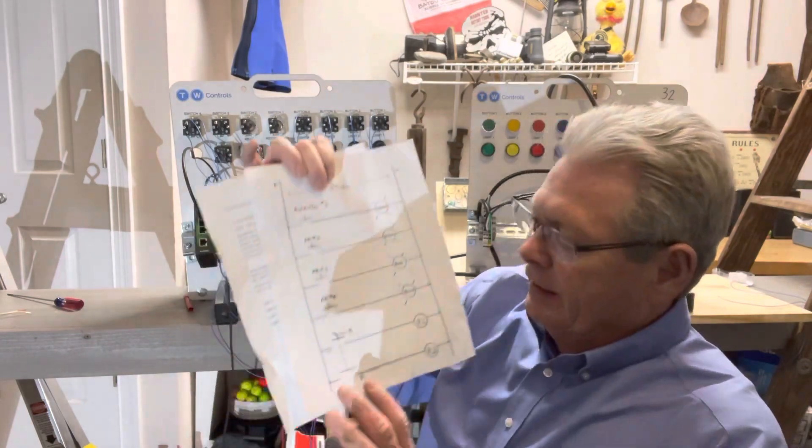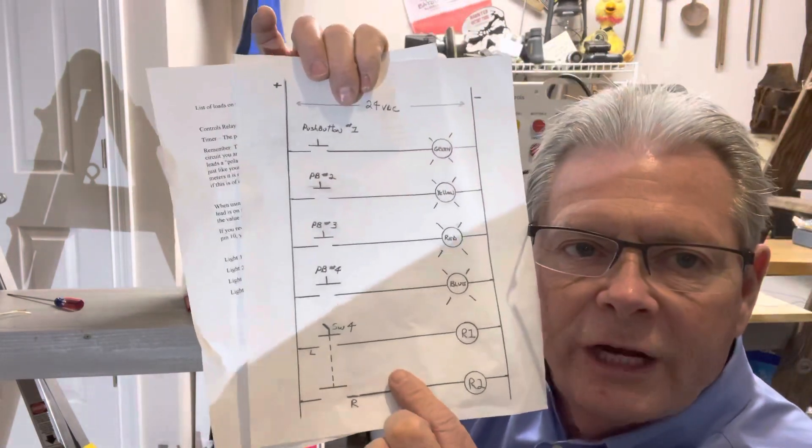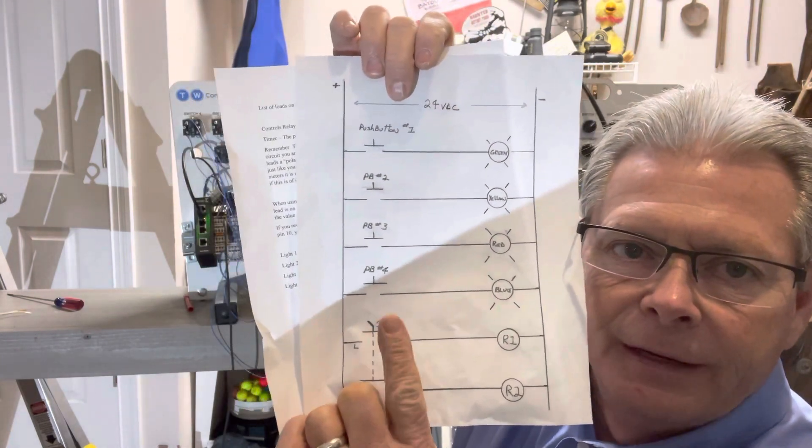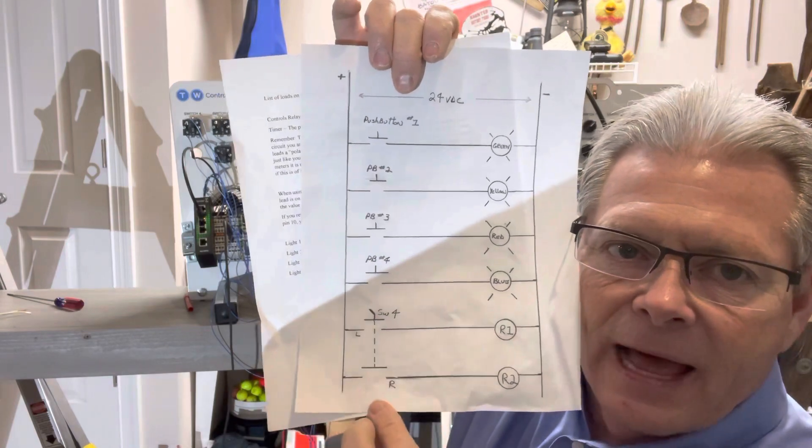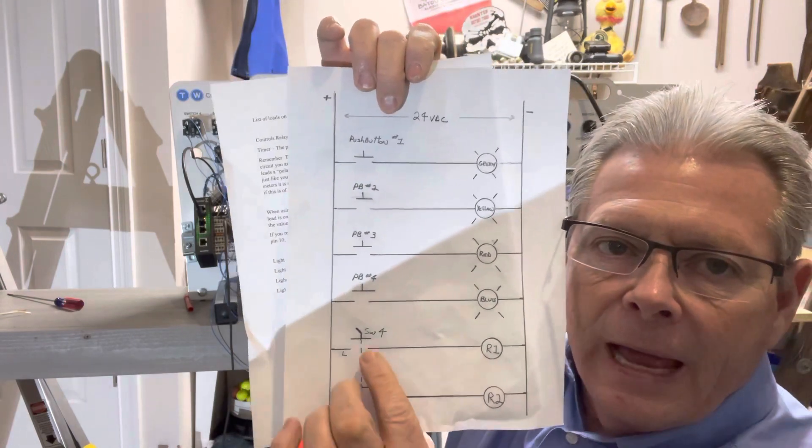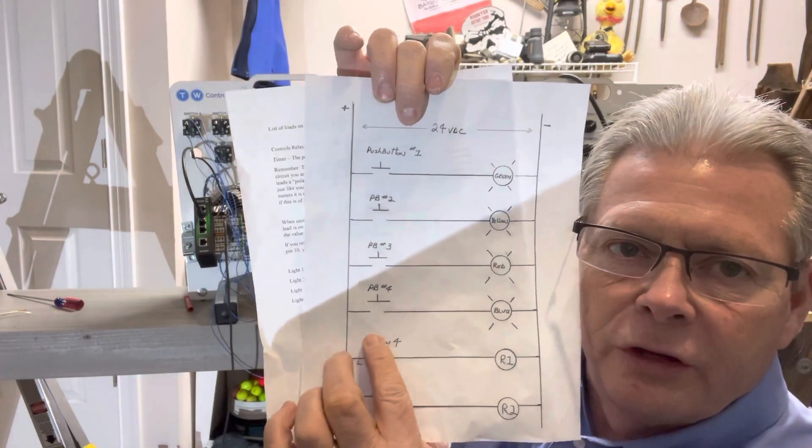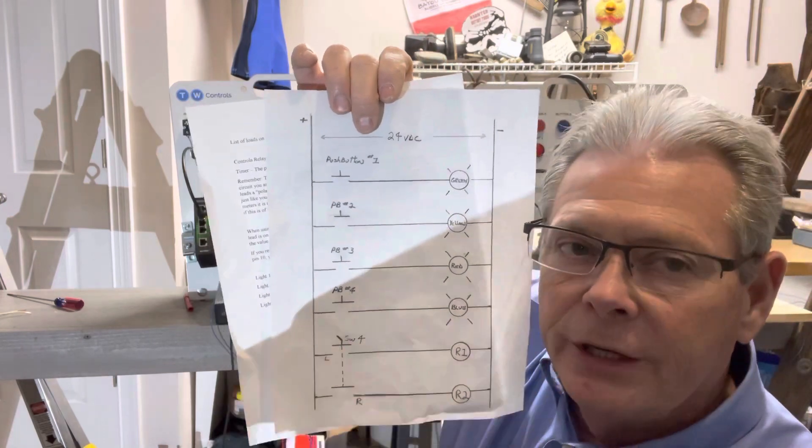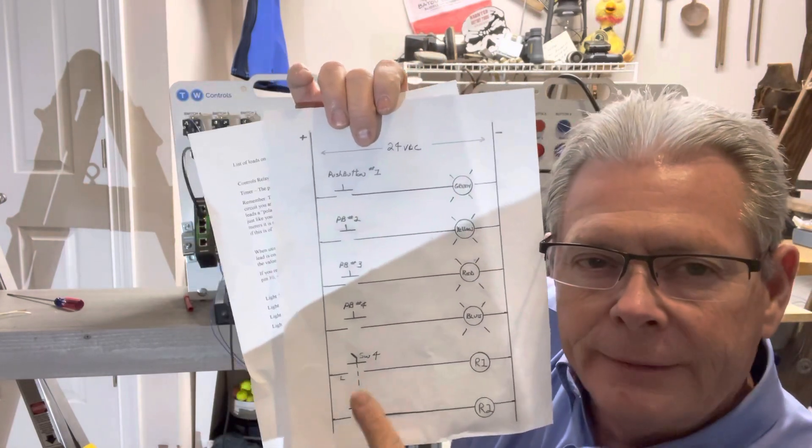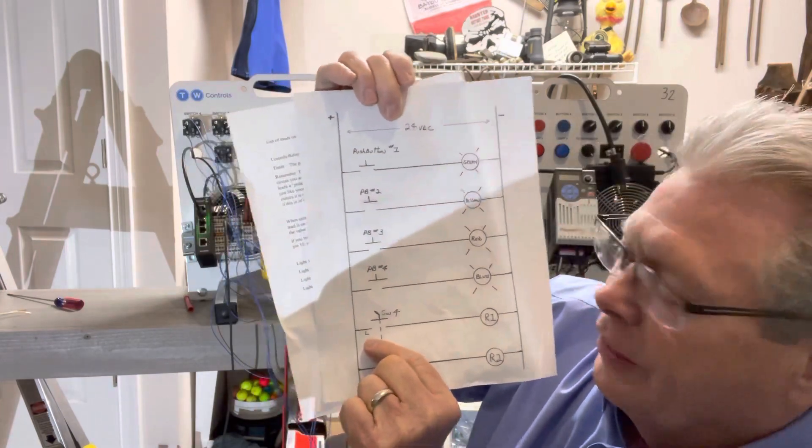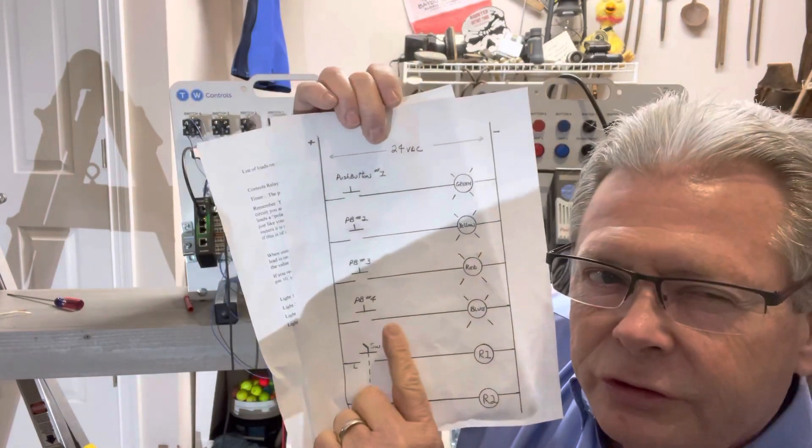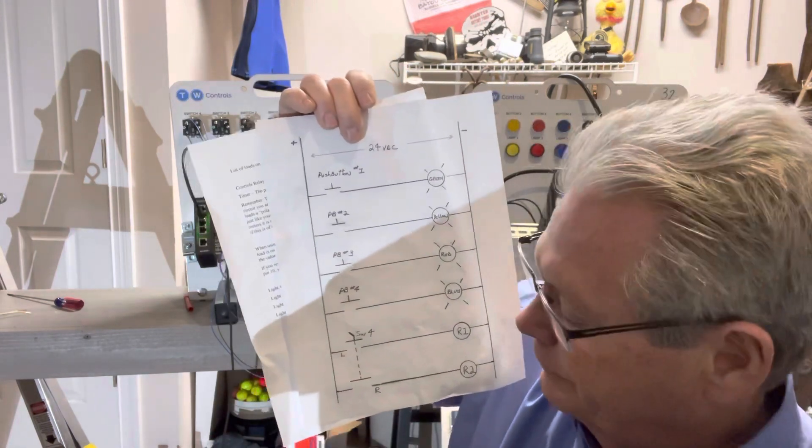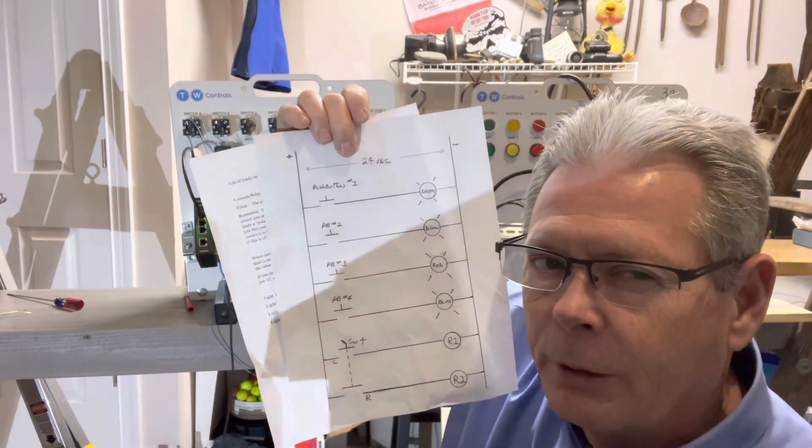Now, the only thing that's left is switch 4. Switch 4 is the selector switch. If you notice on my print, I've got L here and then a dotted line down here and R. A selector switch is different to a push button. This L means when that top of that selector switch is to the left, then this is closed. In the center of its three position, they're both open.